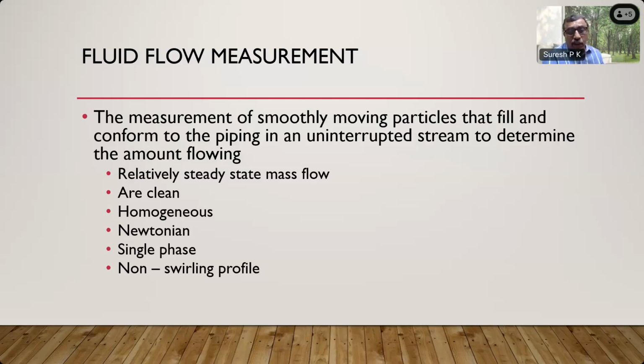Then another thing is non-swirling profile. We assume that the flow which is coming is properly treated and is not rotating. Swirling means the velocity is rotating, a disturbed flow with rotation. That is also not good for flow measurement accuracy. So when you are making flow measurement, you are assuming that it is a steady state mass flow, the fluids are clean, the fluids are homogeneous, you are making the flow measurement on Newtonian fluids, the flow is single phase and it's a non-swirling profile. These are the assumptions which you make when you are making fluid flow measurements.